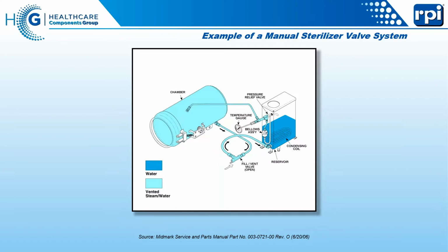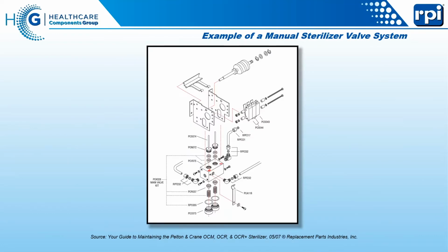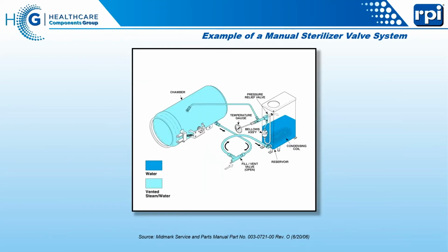Okay, so this is where we started from - the simplest version of what we consider a sterilizer, the Midmark M7. What we have here is a reservoir filled with water, a place where we can get water from. We have one single valve that allows us to let water into this chamber. There's a door, of course, not illustrated, into the chamber. Inside the chamber there's a heating element. We shut the door with a gasket, heat that water, and it circulates inside around here.